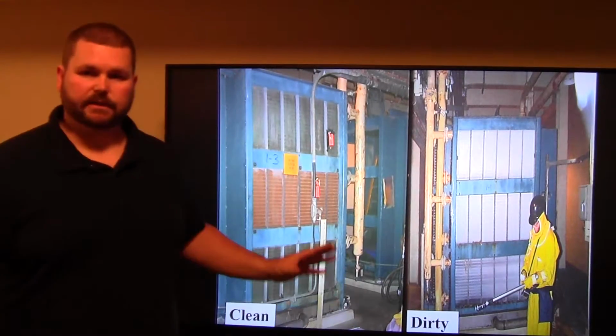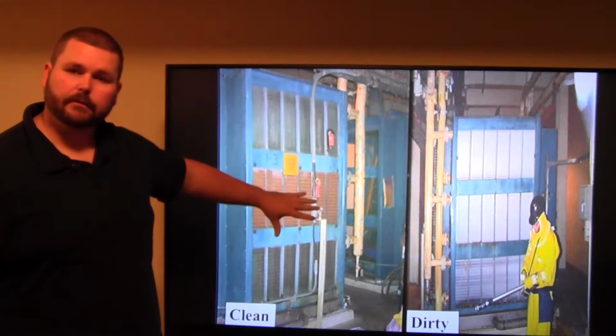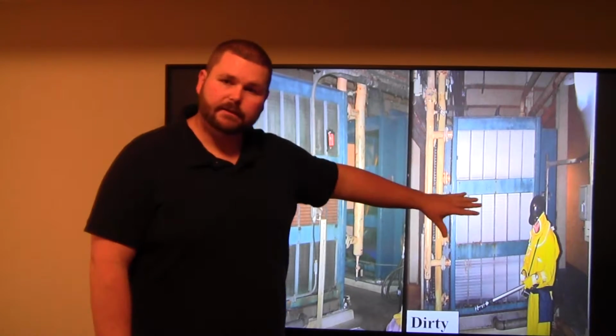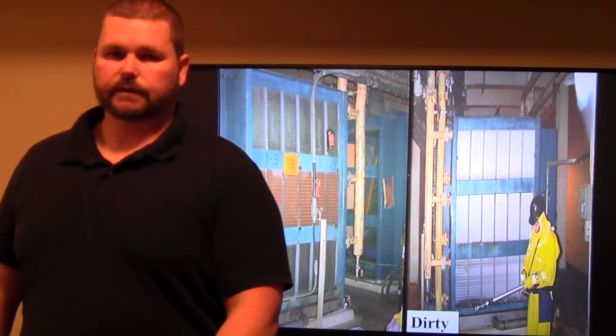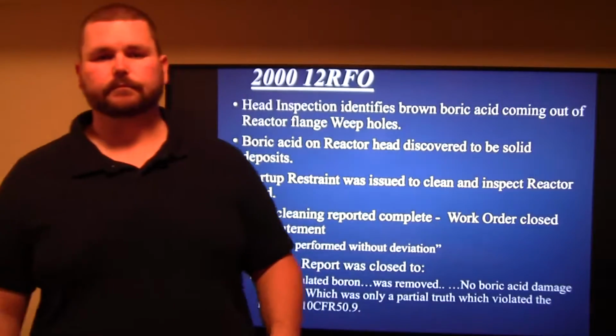And you can see here's actually the containment air coolers, where this is a clean one here on your left. This one on the right is actually corroded, or not corroded, but covered in boric acid. Significant amount. That's just in the air.